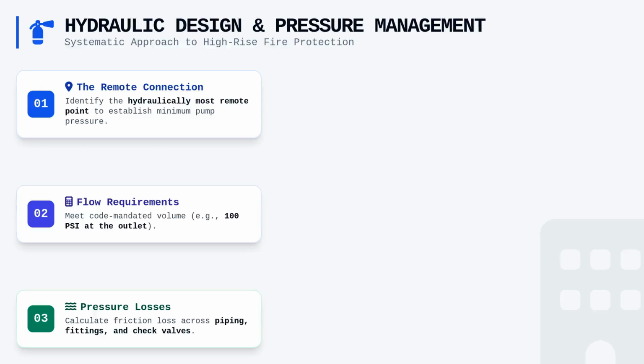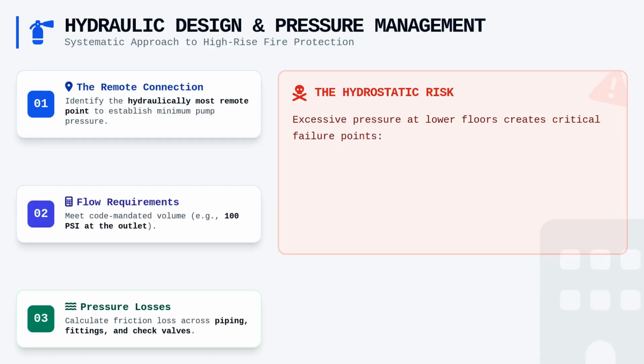Once the remote connection is satisfied, we must account for the pressure losses that occur as water travels through the piping, fittings, and check valves. In modern high-rise buildings, this often creates a scenario where the pressure at lower floors would exceed the safe operating limits for standard hose nozzles if not regulated.